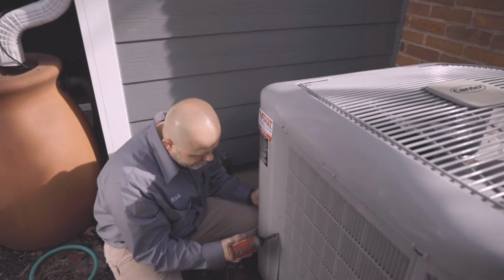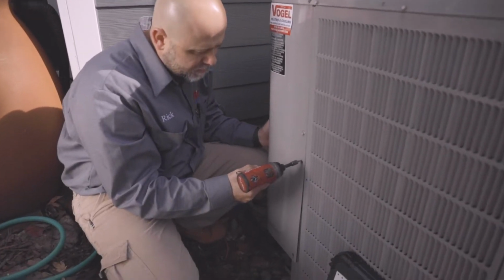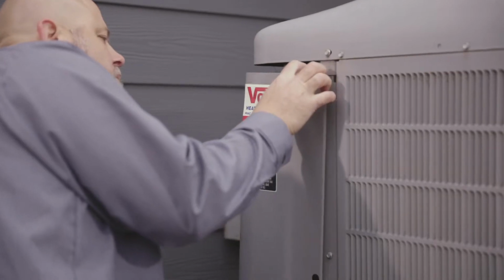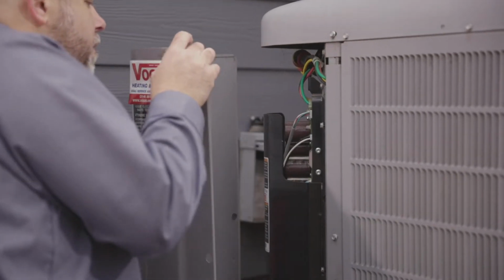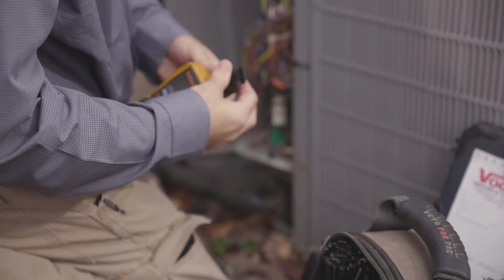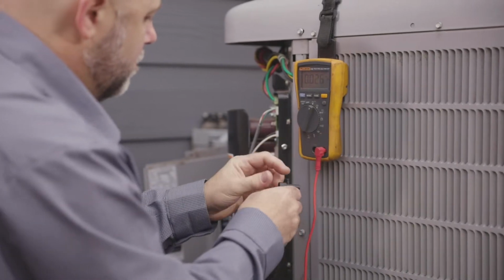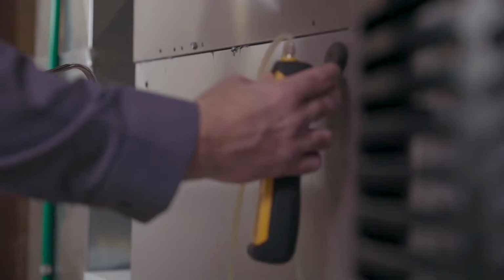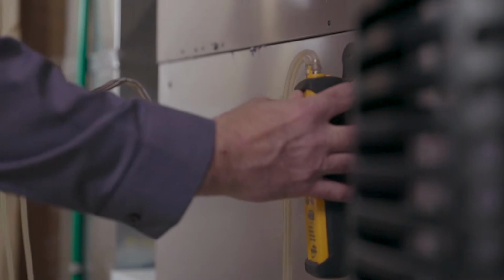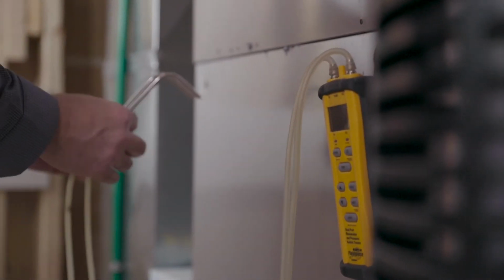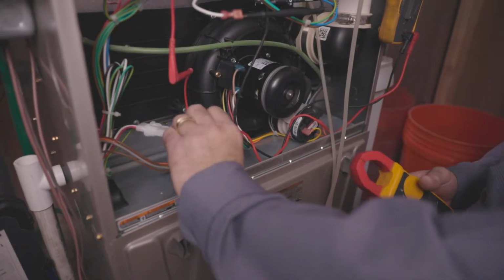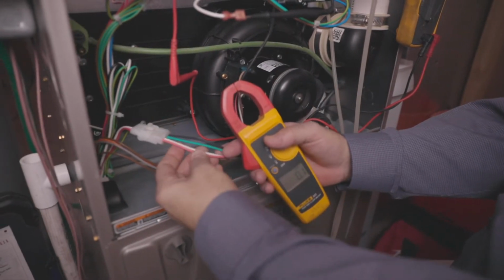An air conditioner can work, but doesn't mean that it's working good. Today, when you purchase an air conditioner, yes, they're rated from the manufacturer, but there are quite a few other things that have to be done in order to assure that efficiency. Well, efficiency, it's installing the equipment the correct way. It involves making sure that your return duct is sized properly. If your return duct isn't sized properly, then your blower motor is going to work a lot harder than it should. In return, it's going to be bad on the system. It's not going to last as long as it should.